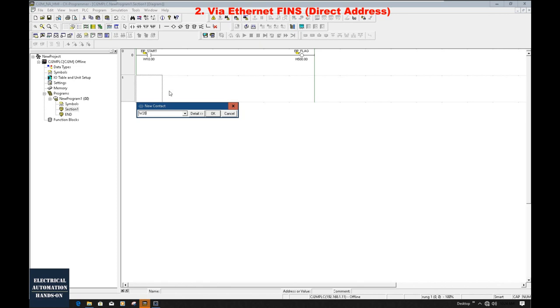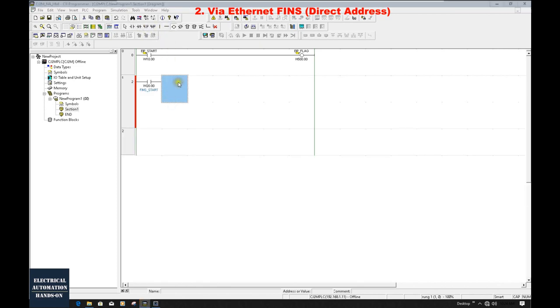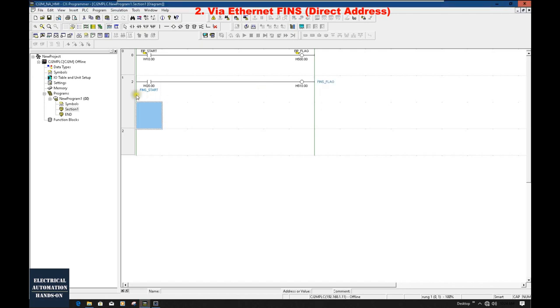From the CX Programmer side, let's create the FINS-style tags. I'll insert a symbol: W20.0 with comment 'FINS_start.' And another: H510.0 with comment 'FINS_flag.' For this communication style, the tags do not need a tag name — they only need comments and the absolute address. In the program: W20.0 controlling H510.0. You'll see the comments shown in blue color — this is the difference between tag name and tag comment.